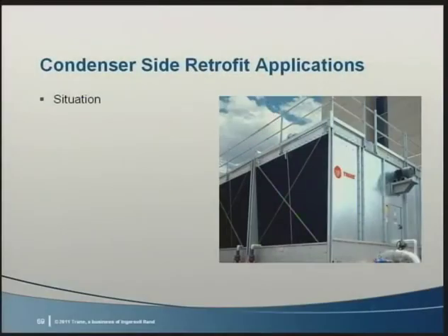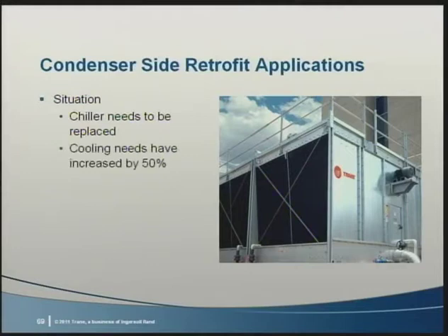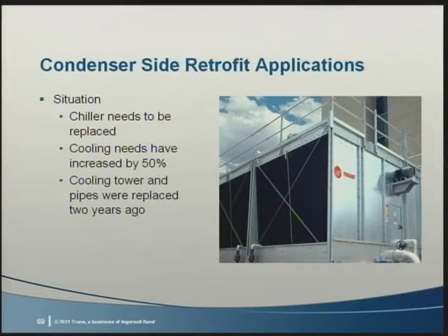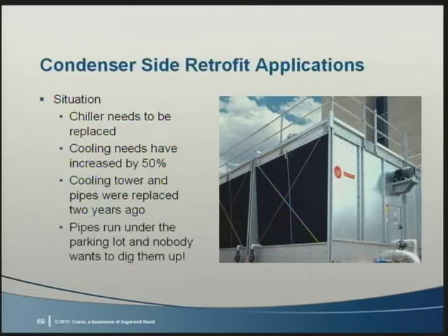Here's the situation. It's time to replace the chiller, but the cooling load has increased. The cooling tower had rotted out 2 years ago and was replaced, so it's in good shape, as are the new condenser pipes. The condenser piping goes under the parking lot, and nobody wants to rip up that parking lot again. This situation probably sounds familiar to at least one person in the room. Often the first thought is that the entire system needs to be replaced, and the job goes out of budget.